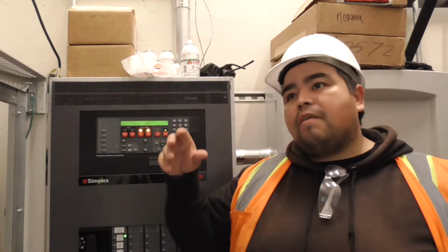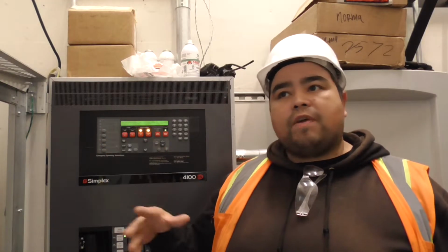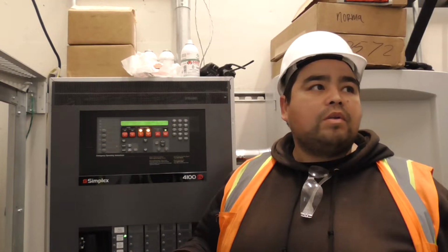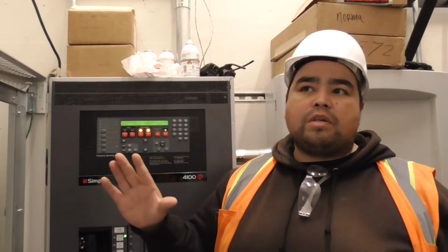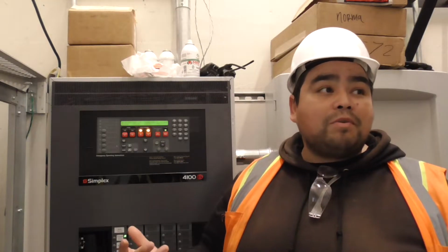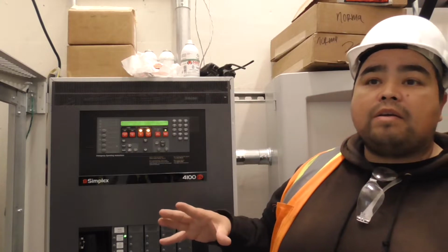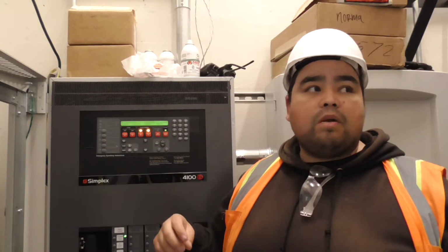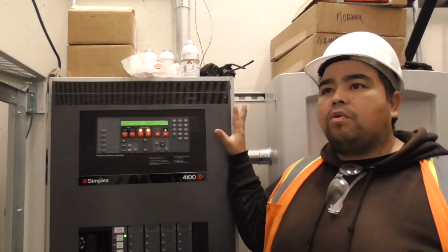Okay. And then if your smoke detector goes off, it does a code 3, which is like a universal evacuation code for fire alarm. So that's what the building does. It does a code 3, or it's going to do the code 4 so you can tell the difference between what event is happening. I'm not sure if the students will recognize that, but that is how it works. Code 3 for fire, code 4 for CO or gas leak. Okay. So that's pretty much the only thing different.